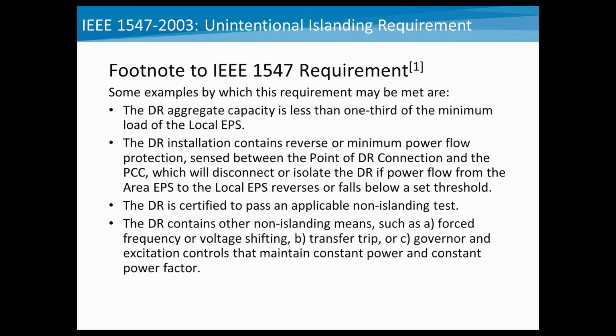Okay, so in addition to the requirement, there's a footnote in 1547, and the footnote is very important to read because it gives some suggestions on how to meet the requirement. So for example, you're able to meet the requirement if your DR capacity is less than 1/3 of the minimum load of the electric power system, so the DR is small in relationship to the local load. Also if the DR contains minimum or reverse power flow protection, if the DR is certified to pass an applicable non-islanding test, and if the DR contains other non-islanding means, such as forced voltage or frequency shifting, transfer trip, or governor excitation control. And we'll talk a little bit more about these in a couple of slides here.